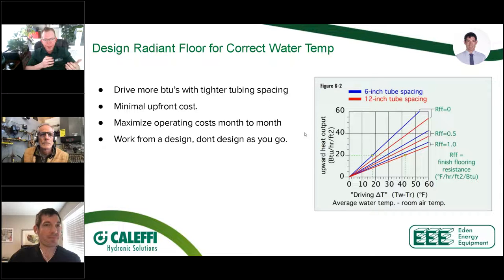Yeah. The way they came up with that 300 feet wasn't just a bunch of us getting together and saying, oh, 300 seems good. As you tighten up that spacing, if your circuits don't shorten, your head loss goes through the roof. So you do need to make sure you don't just go, hey, I heard Mike say do more pipe. Because I have seen, Jason, we had a designer many, many years ago who did not care what I said to him. He did 3/8 tubing as tight as he could, and he had 600-foot circuits. The reality was he couldn't pipe it. There was no way he could pump it.